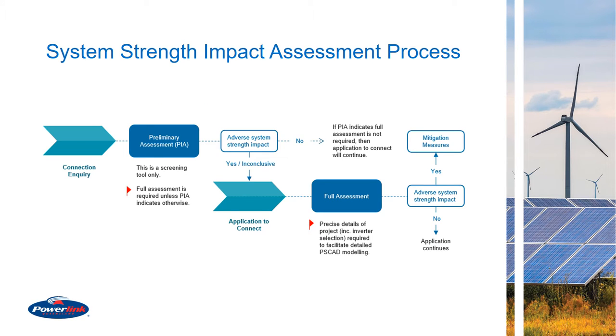This diagram is showing the whole process of system strength impact assessment. As I previously said, the connecting NSP has an obligation to conduct the preliminary impact assessment, which is PIA, that is done at the connection inquiry stage. And if PIA concludes that FIA is not required, then the application can progress without doing the full impact assessment. However, if PIA concludes that either FIA is required or it is inconclusive, then that full impact assessment must be done at the time of the application by the connecting NSP.